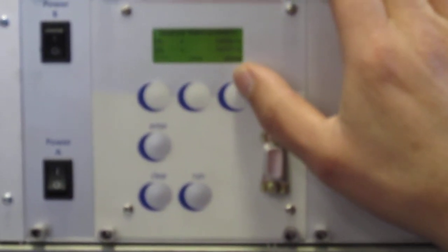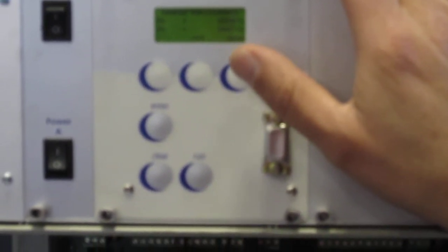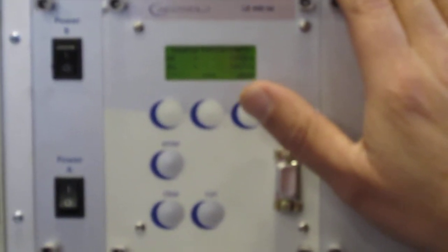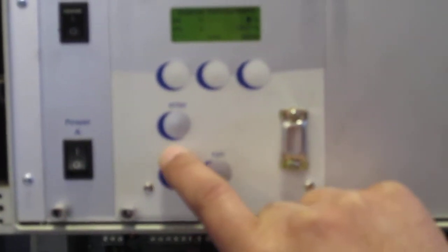Source replacement. This is where when you do a calibration, it calibrates when the source is decayed. You have cesium, that's 30.17 years, so it's a long time, but every night at midnight, as I said, it takes the decay rate out. So when you do a calibration, it sets that. The thing to know here, you really don't have to worry about this, is that if you don't say clear and put a 0 there and enter that, then when you do your calibration, it holds the last number.